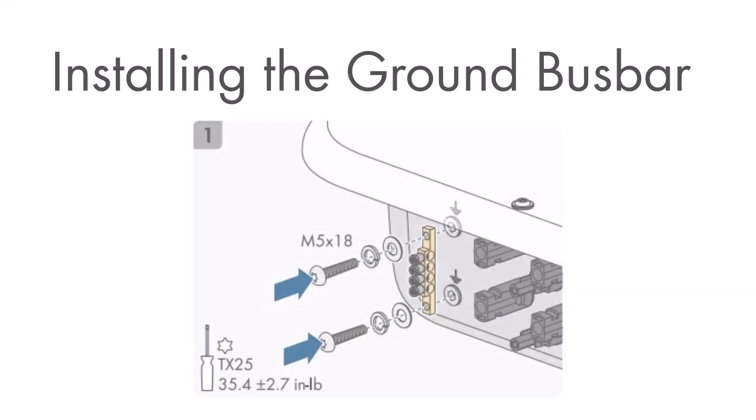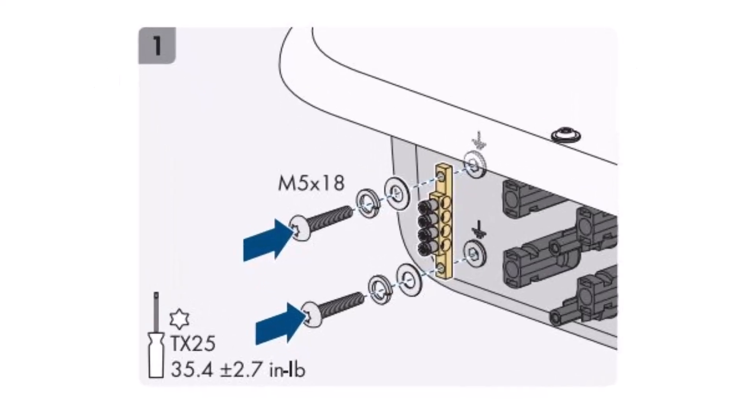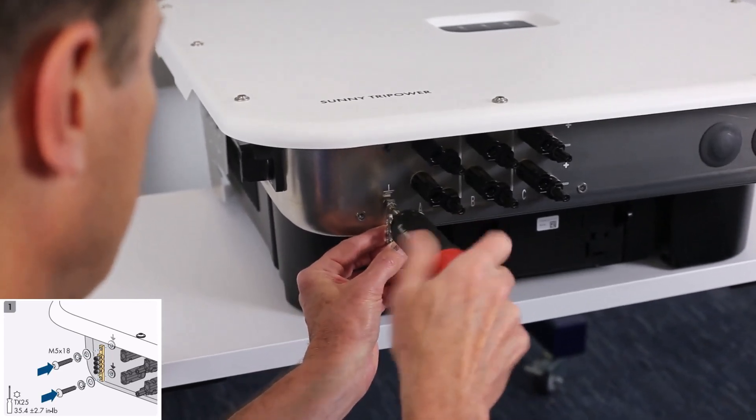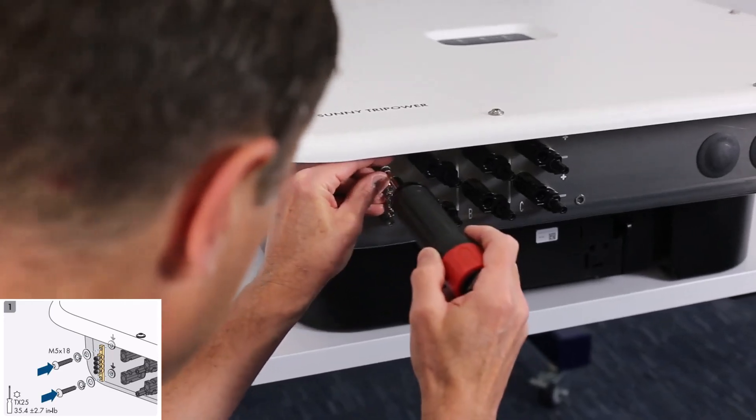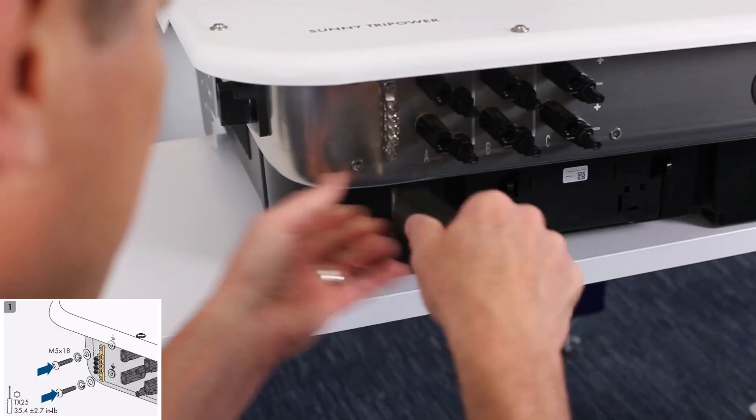The first installation we recommend doing is the ground bus bar. You would need a Torx 25 screwdriver and the two included M5 x 18 screws and washers. Begin by inserting the washers through the screws and secure the screws to the inverter with a Torx 25 screwdriver. For ease of installation, lay the STPX flat, such as on a table, and proceed to install the ground bus bar on the bottom left of the inverter. And tighten to 35 inch pounds.